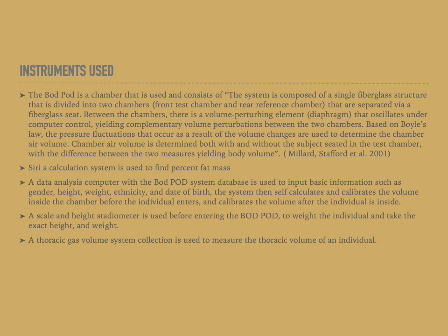Instruments used: for BODPOD testing, you of course need the BODPOD. The BODPOD is a chamber consisting of a single fiberglass structure divided into two chambers: the front test chamber and the rear reference chamber, separated by a fiberglass seat. Between the chambers there's a volume-perturbing element called a diaphragm that oscillates under computer control. This yields complementary volume perturbations between the two chambers, and based on Boyle's Law, the pressure fluctuations that occur as a result of the volume changes are used to determine the change in air volume. The chamber air volume is determined both with and without the subject seated in the test chamber, with the difference yielding the body volume.